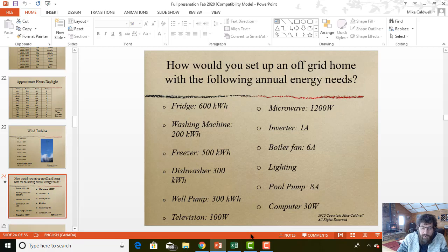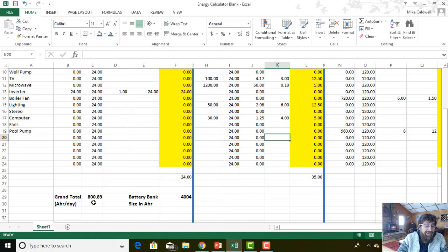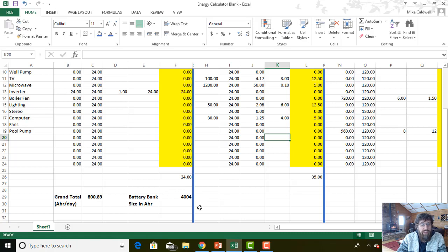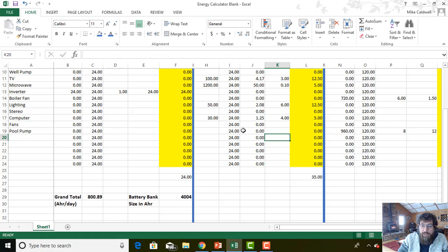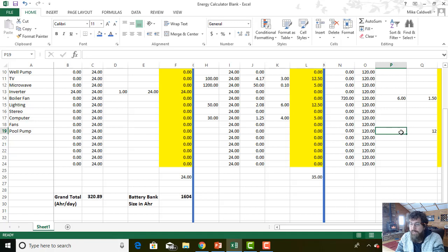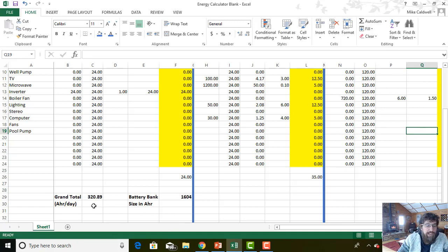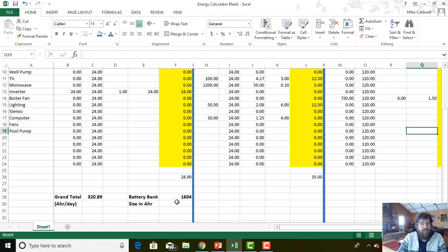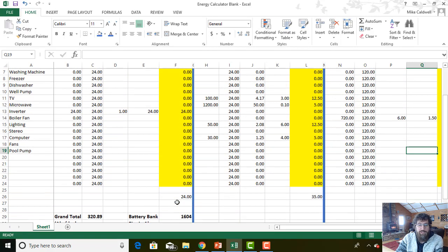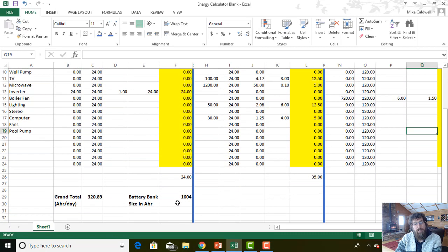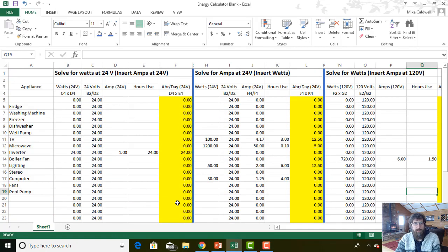For this house, how big a battery bank do we need? We are burning 800 amp hours per day, which means we need a huge 4,000 amp hour battery bank. That's quite big. My battery bank is 1,200 amp hours. So let's get rid of the pool pump. So now you can see how we're now only using 320 amp hours per day and that we have a battery bank sized at 1,600 amp hours. My battery bank is 1,200 amp hours, so it would be just marginally small for this system, but it would still work.